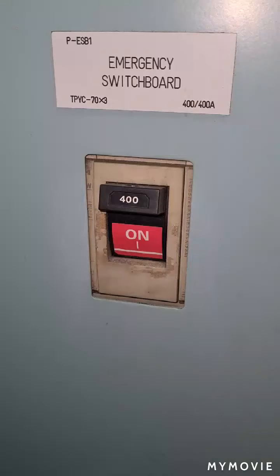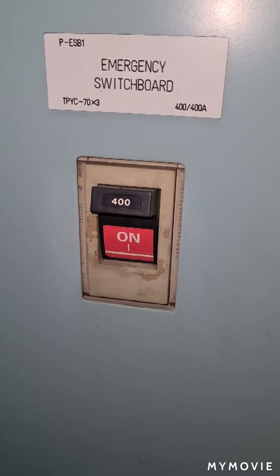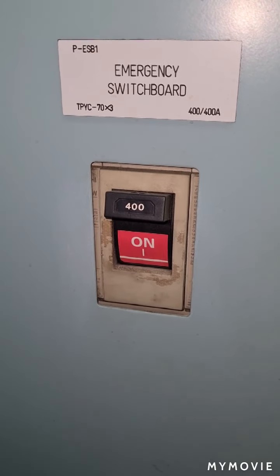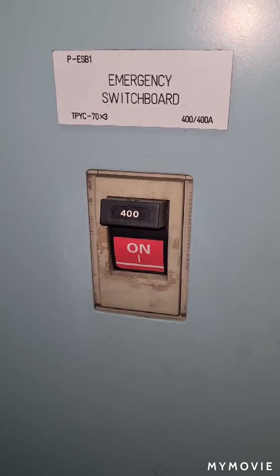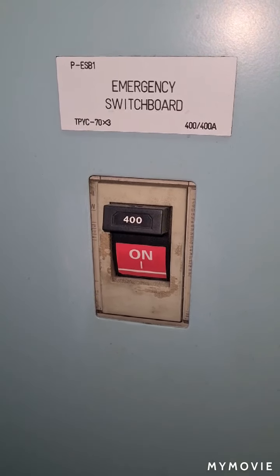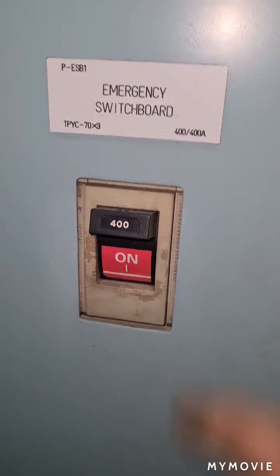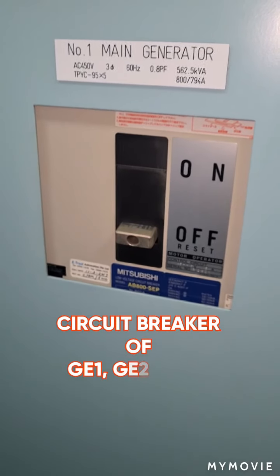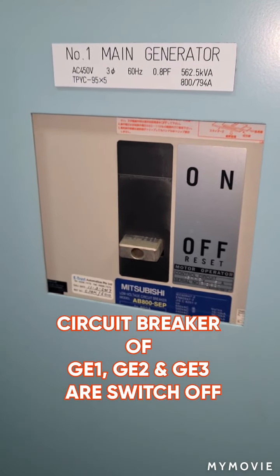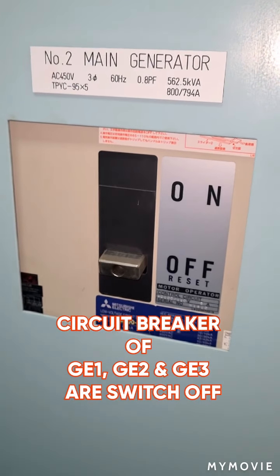If all those things are off, you can now proceed to connect the power cable from shore going to your shore connection terminal box. Shore circuit breaker. Before you are going to connect the shore connection on the bus bar inside of the shore connection box, make sure that this circuit breaker is off. Make sure also that number 1 generator and number 2 generator is off.